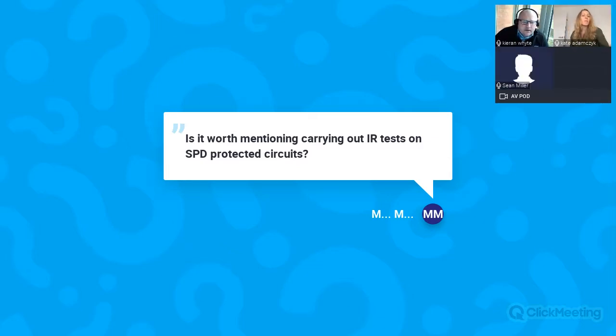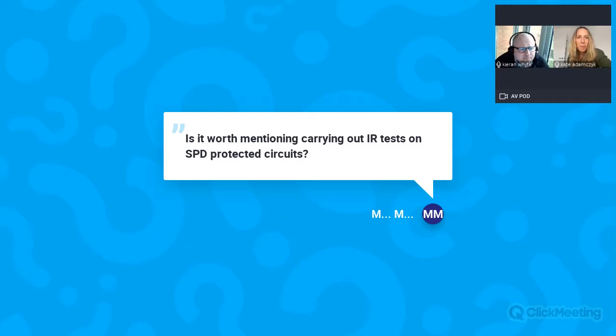Is it worth mentioning carrying out IR tests on SPD protected circuits? Again, it's like having any electronics in the circuit when testing. You need to take them out of circuit, otherwise you could get false readings. If you have appliances plugged in when you're doing an insulation resistance test, you'll read through the resistance of that heater or that kettle on the circuit you're testing, so it'll give you a false reading.